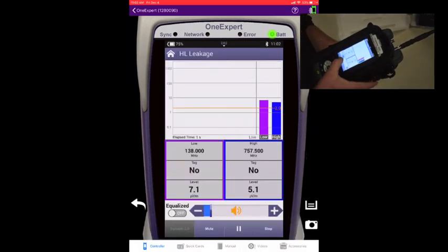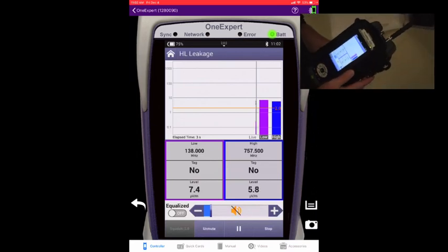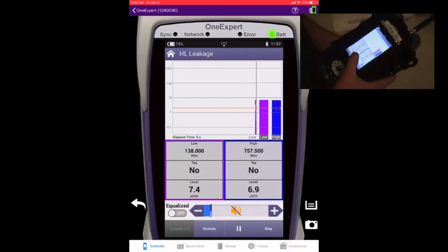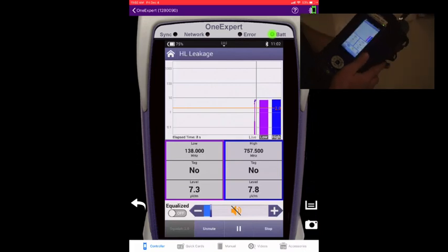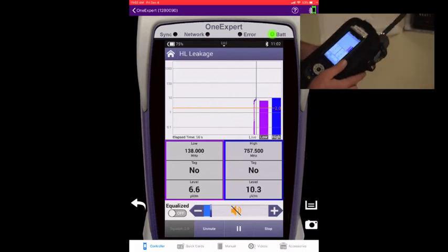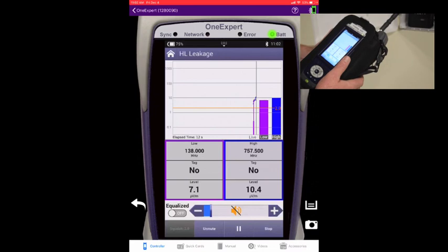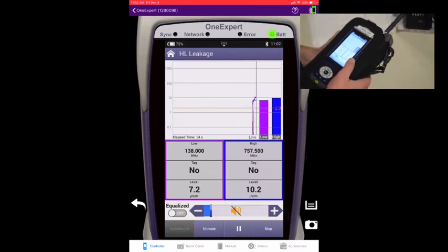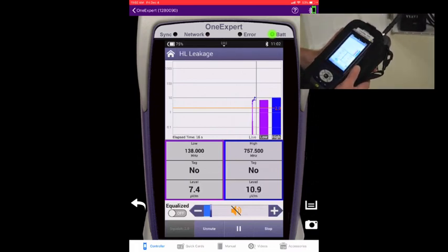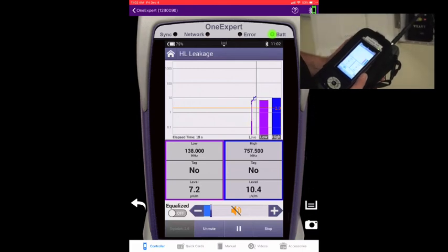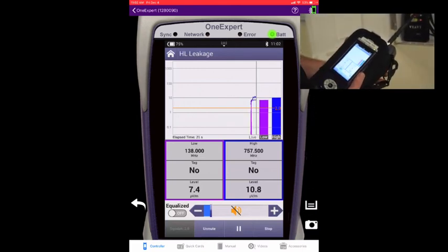Once the app has initialized and loaded, you're going to see a tagger on 2 frequencies. They both say no right now. That means that it's not logging on to the tagger from the transmitter. You'll also see a signal level. This is a microvolt signal level. This is going to help you isolate where the leakage is.